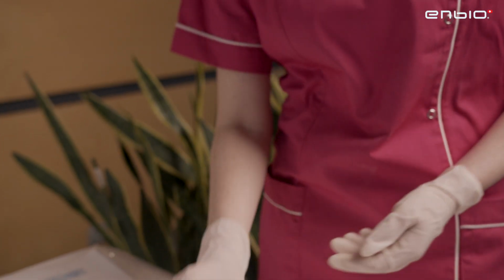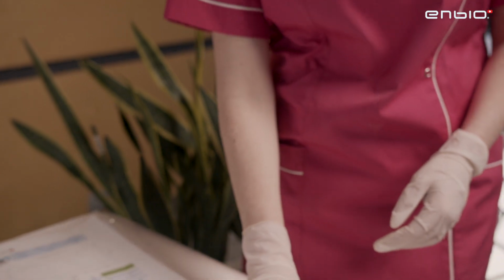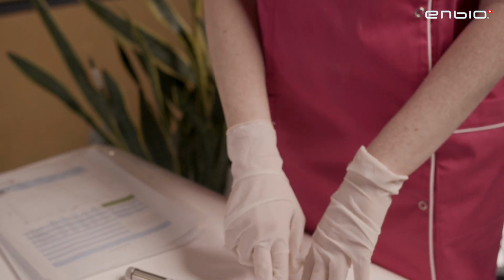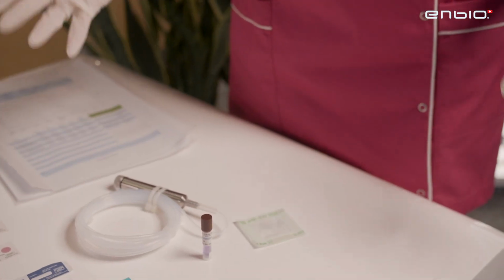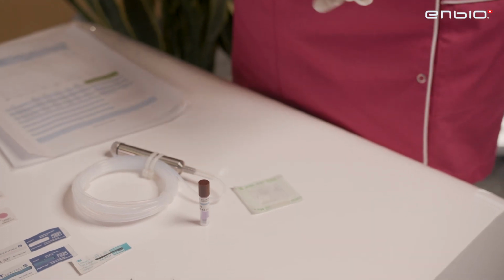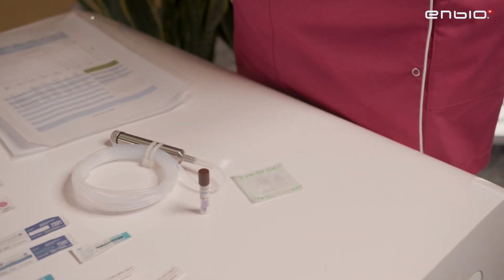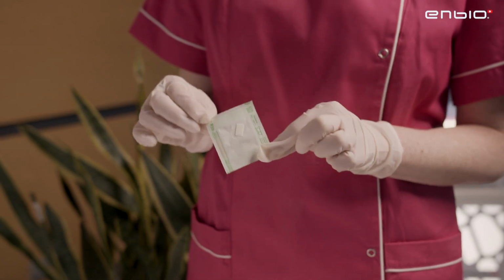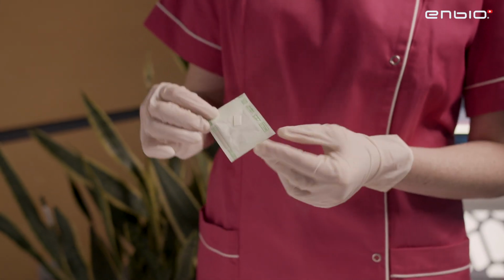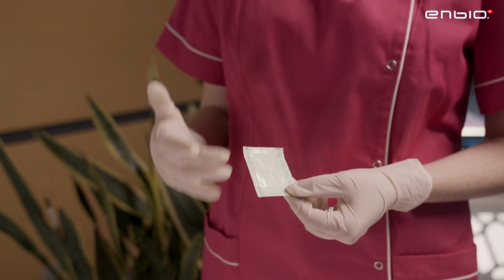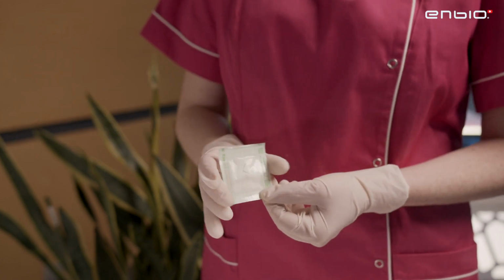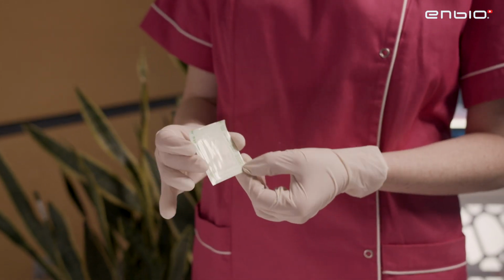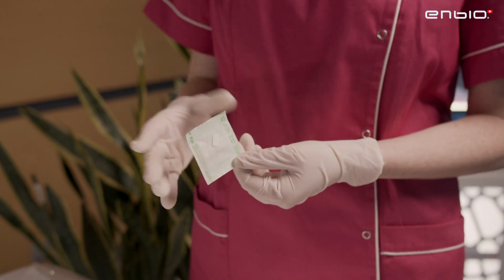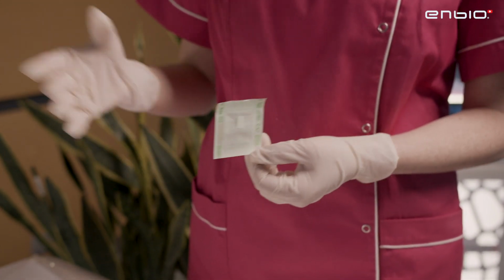And one more important thing is to use the Sporal test with the program that we use most often when we sterilize our tools with an autoclave. And when we introduce this test inside the autoclave, it is better if we also have other tools inside in sterilization pouches so that the test is performed in the natural environment of the sterilization.